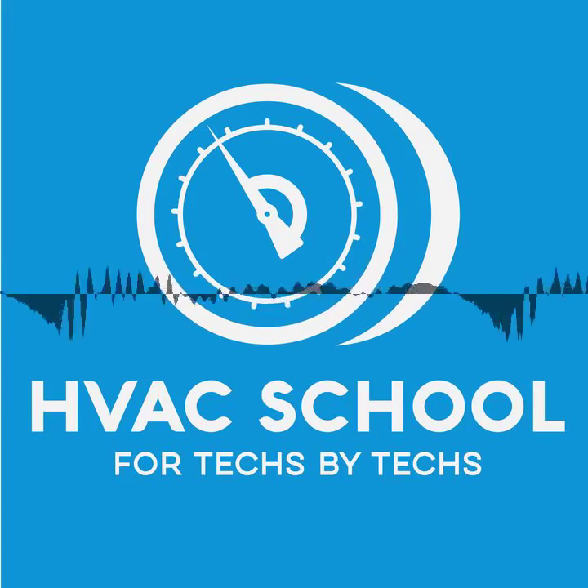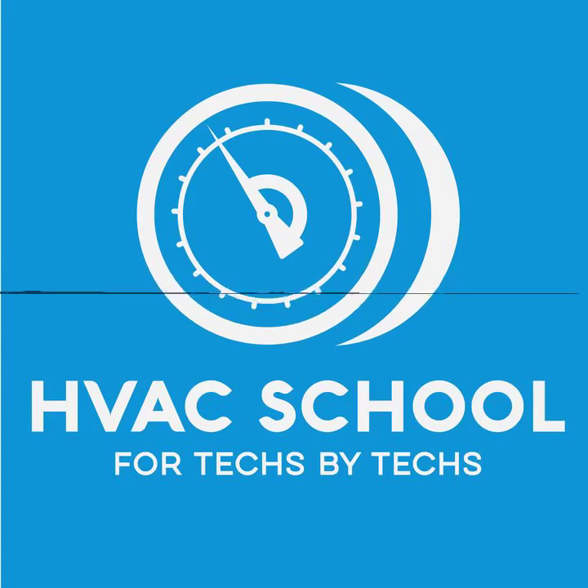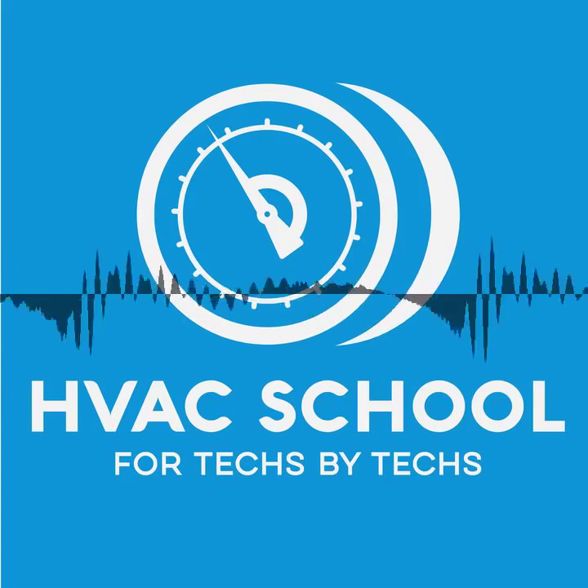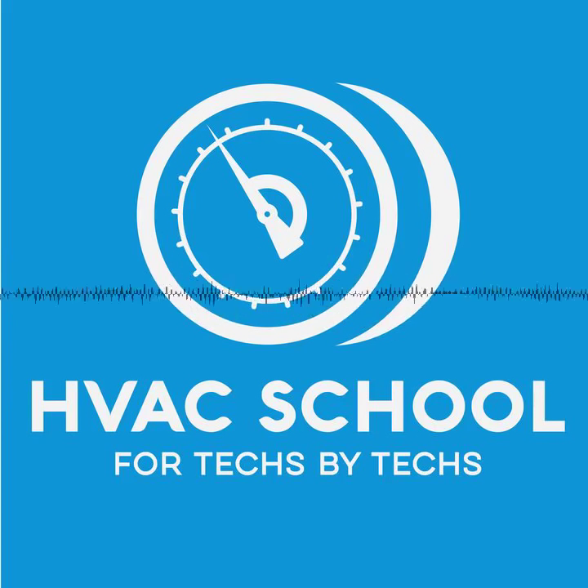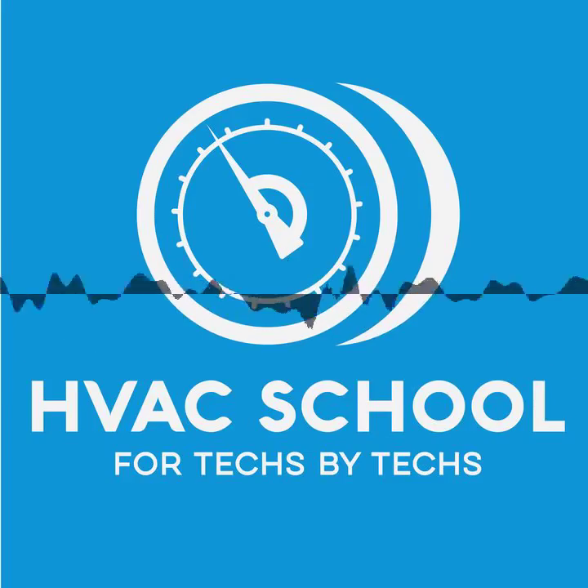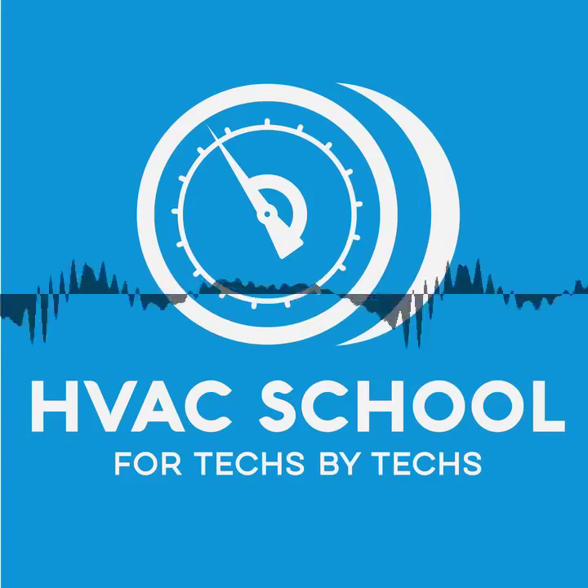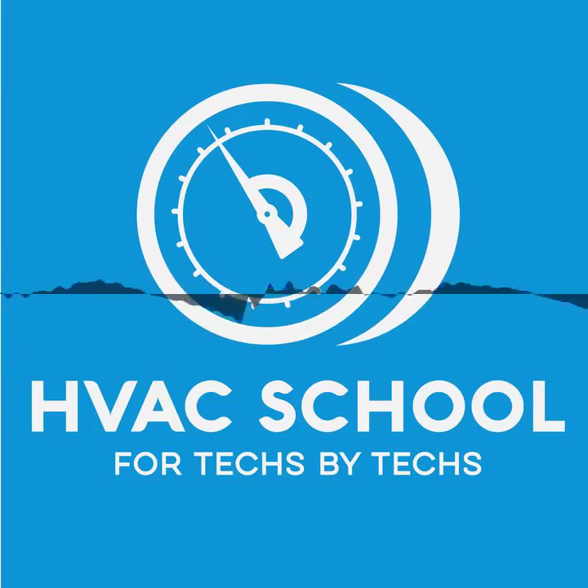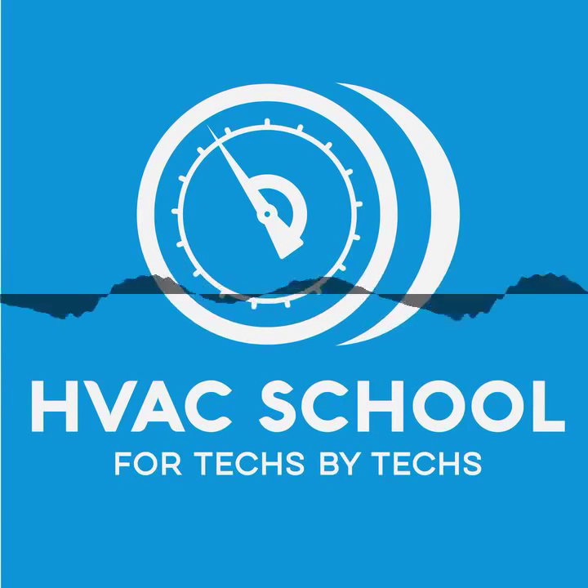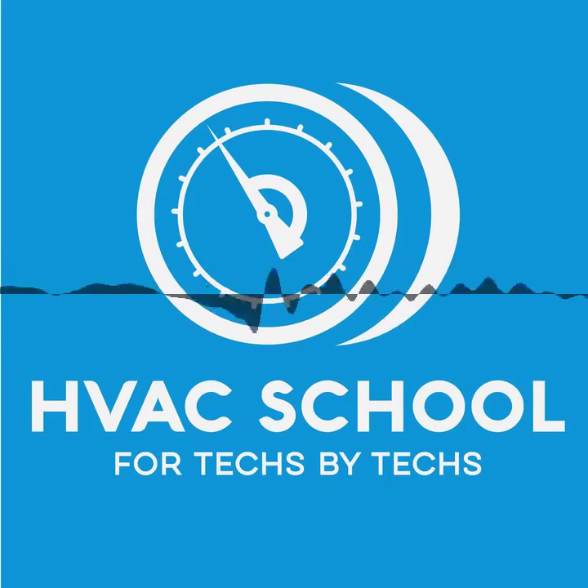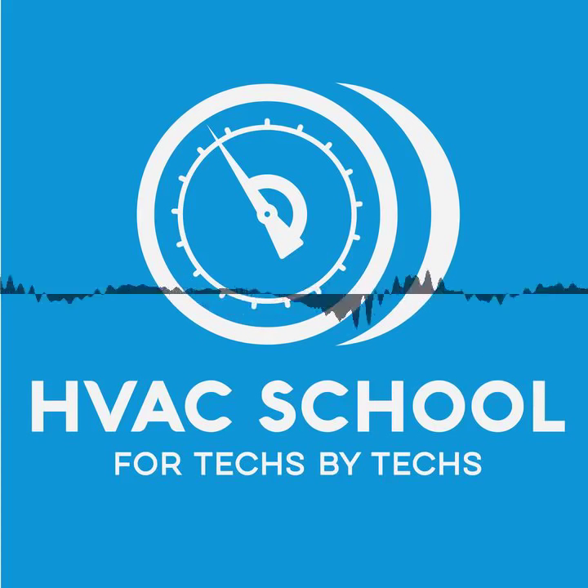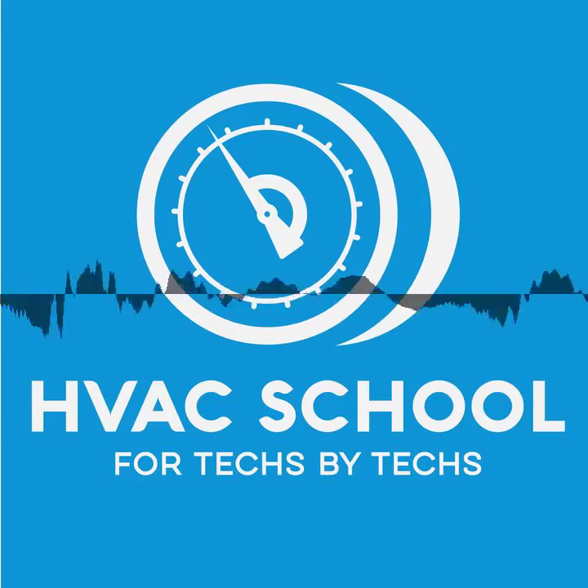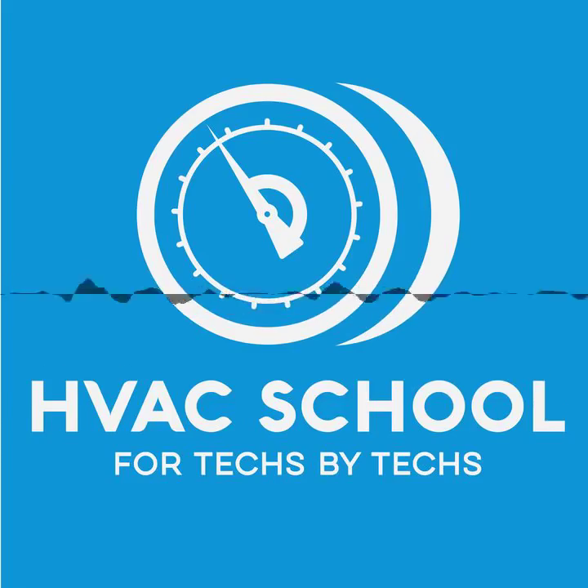I suggest putting in, I forget the exact name of it, but Supco makes a little resettable fuse. It's essentially a tiny little circuit breaker, a little 3-amp. I suggest getting the 3-amp. Obviously, we know a lot of furnaces have 3 amps. A lot of fan coils have 5 amps, but just for testing purposes, just use the 3-amp version. And then plug that into the receptacle for the fuse, your typical fuse receptacle. And then instead of blowing fuses all the time while you're testing, in the case that you do actually find it, you're going to save fuses. And that way you can just reset it as you're testing, which is just a good general practice, especially as you're learning. Yeah, good point.